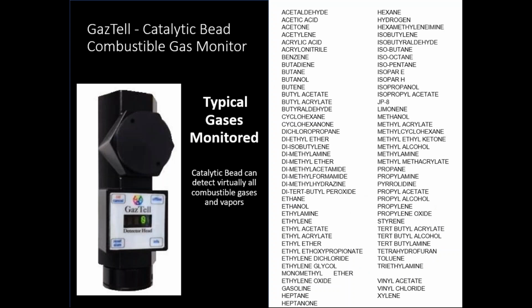Like our 550 system, the catalytic bead GazTell is going to be capable of monitoring generically a whole slew of combustible gases. These gases, if you actually looked at combustible gases and you Googled it, you'll find that there's probably 5,000 different gases that are considered combustible. Although we haven't done them all, and in fact there's probably not a market for all, you can see we've done quite a few. I think we've done about 63 gases over the years for a catalytic bead. So what happens is when you buy a catalytic bead, that catalytic bead can detect any one of these combustible gases that exist on this list, at least.